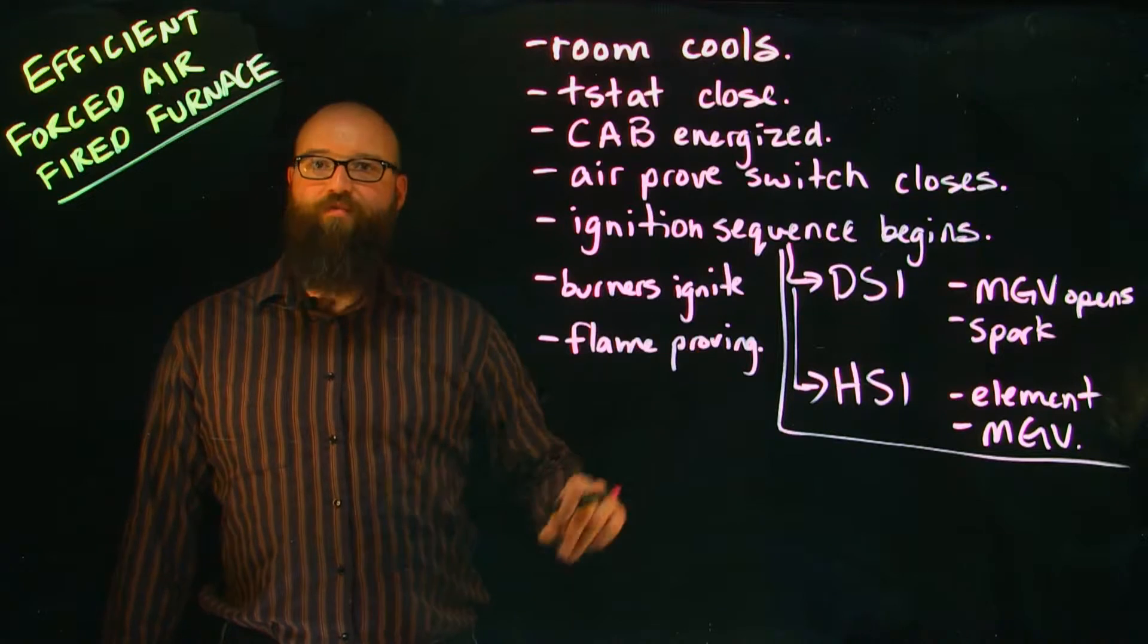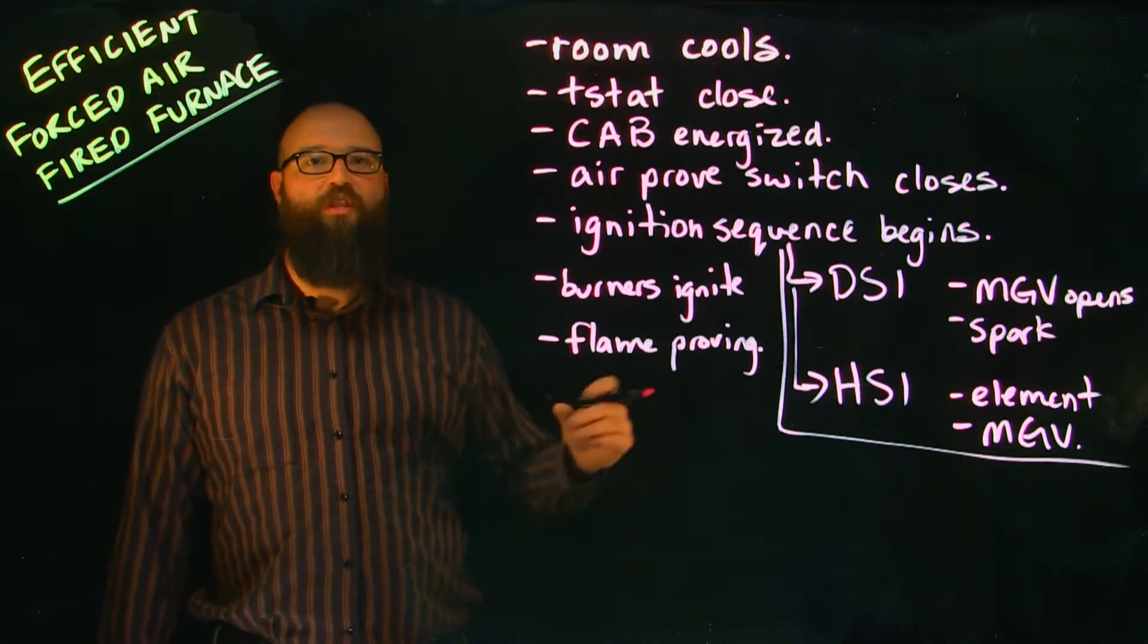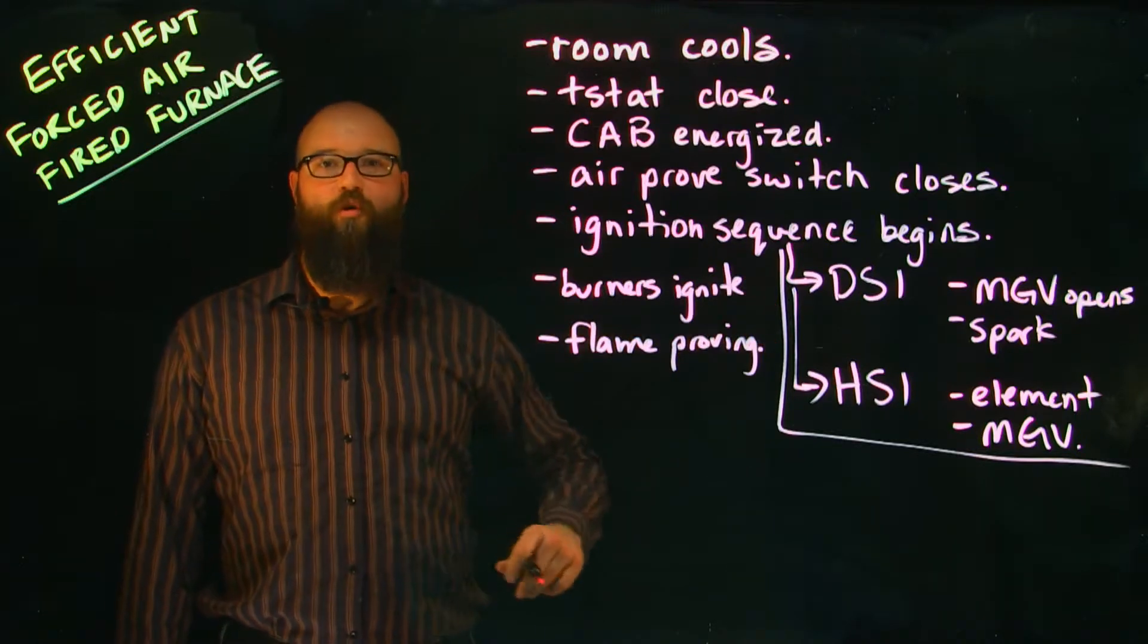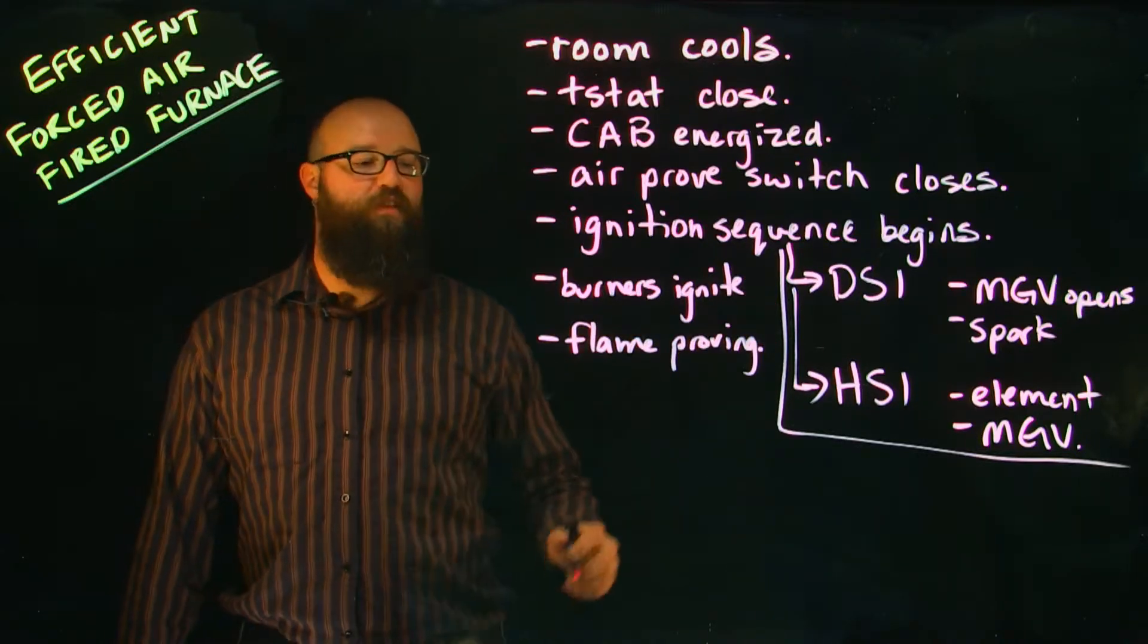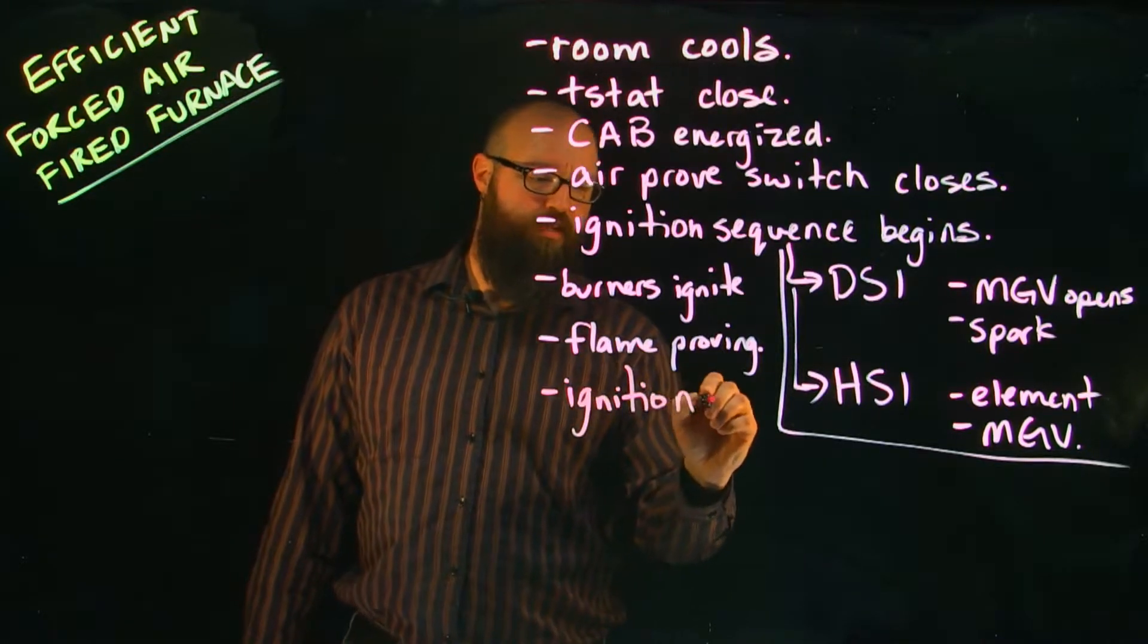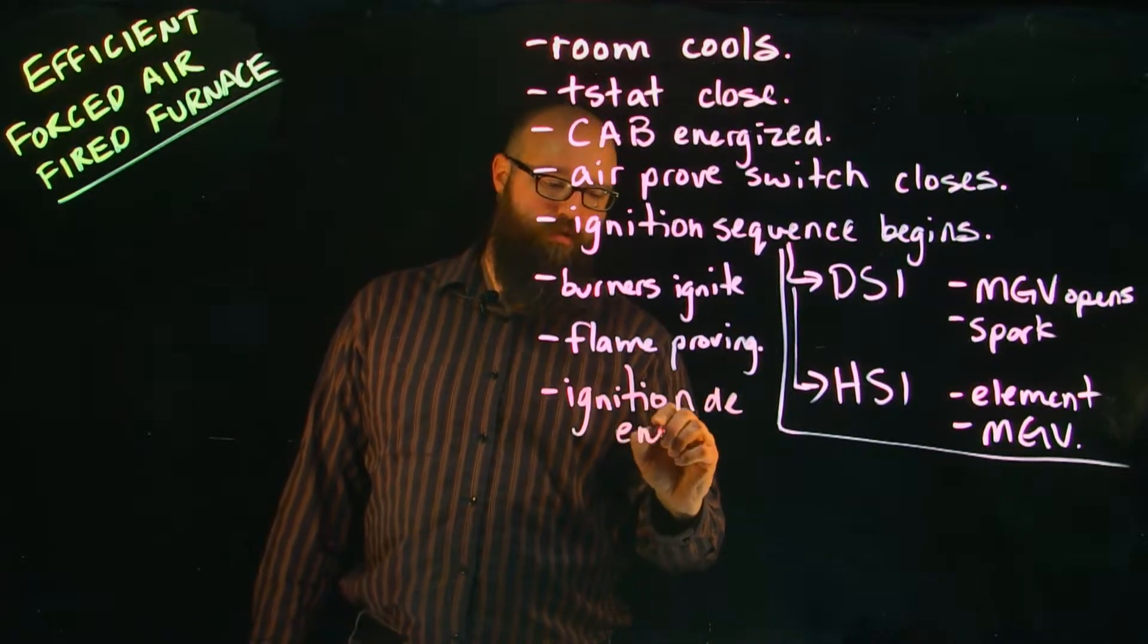We use a flame rod for flame proving. Once it's been established that there is indeed a flame at the burners, the flame proving then sends a signal back to the electronic control board telling it that it's okay to shut off the ignition sequence. So ignition de-energized.